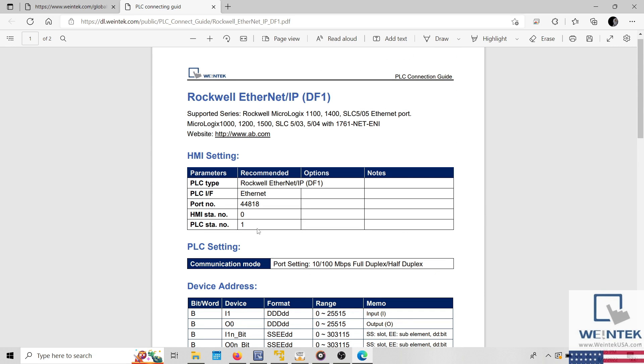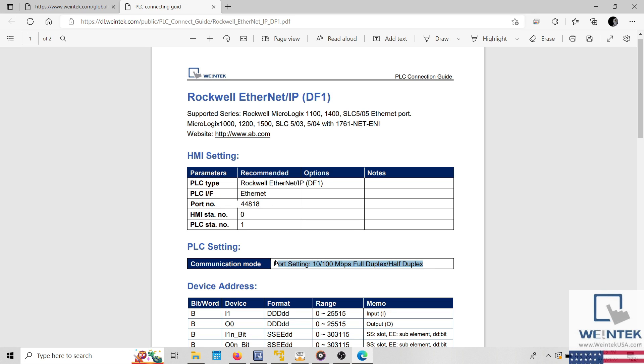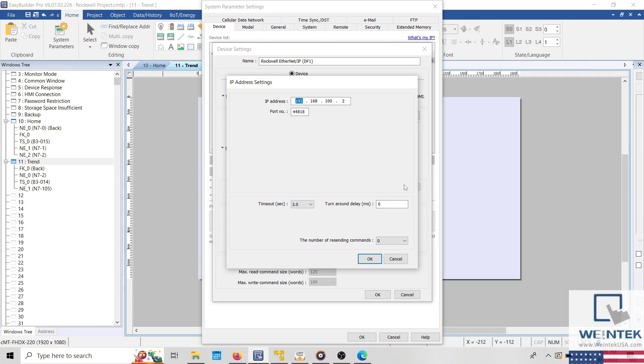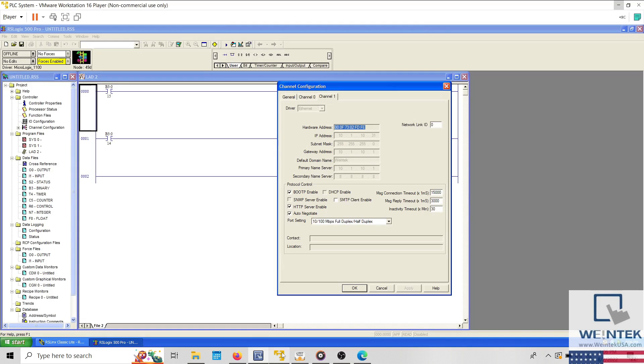Within this specific PLC connection guide, we should note the following. The recommended port number is 44818 and within the PLC software, the port setting should be configured as shown. When using an Ethernet interface, the port number should be set by default to the port number that is recommended within the PLC connection guide. Within the system parameters, we can see that our driver has been configured with the appropriate port number. And within the PLC project, we can see that the correct port setting has been selected.